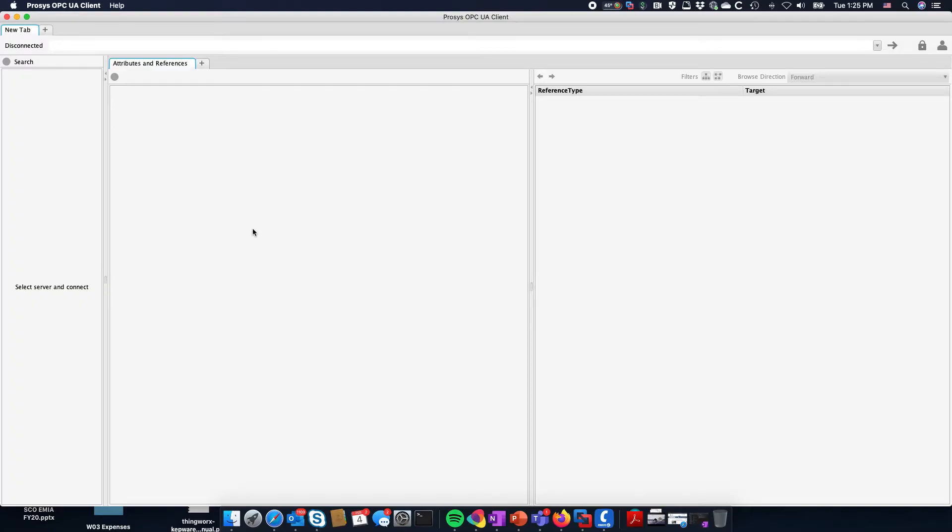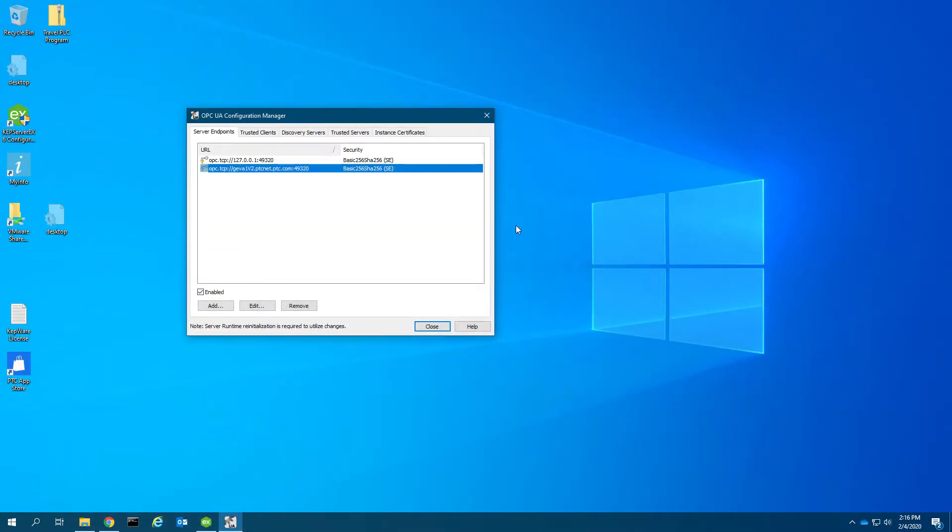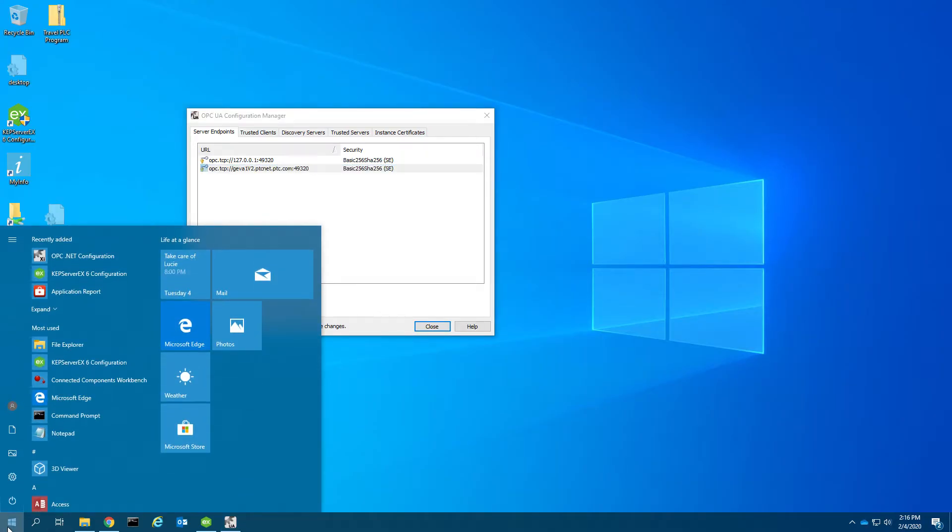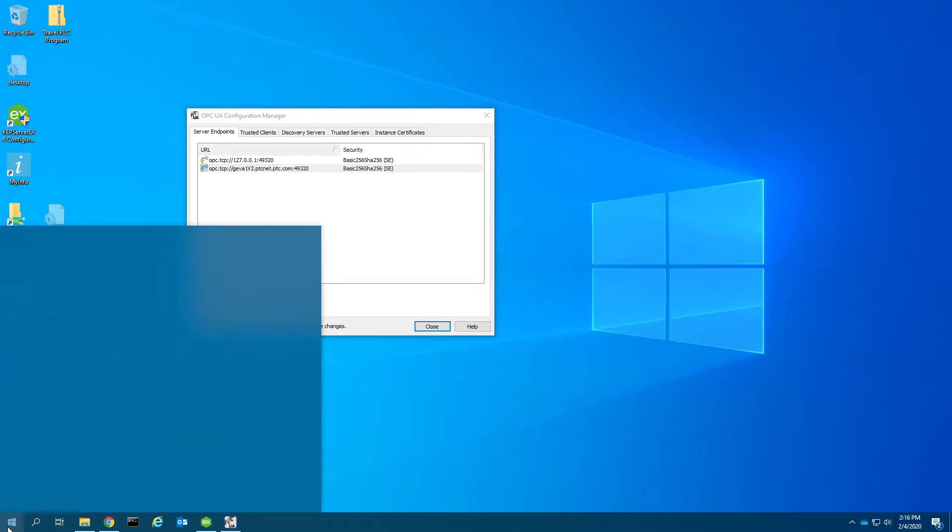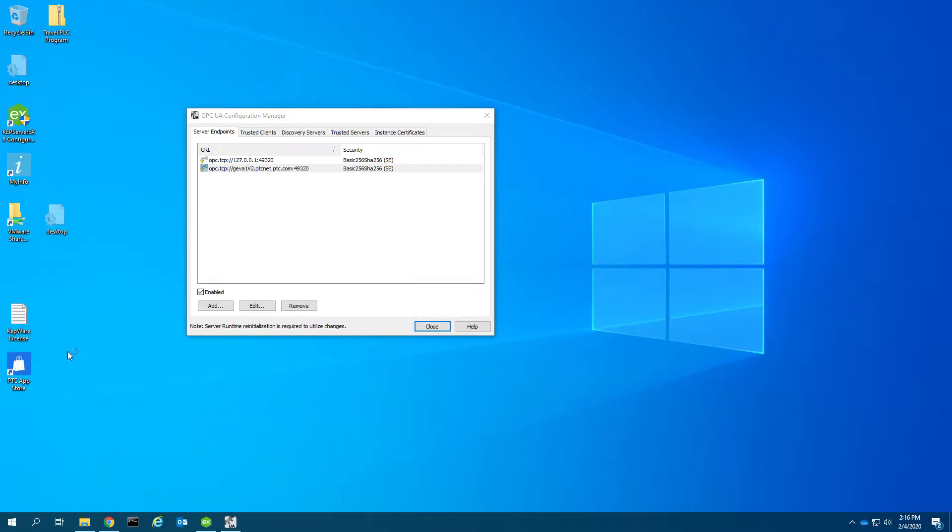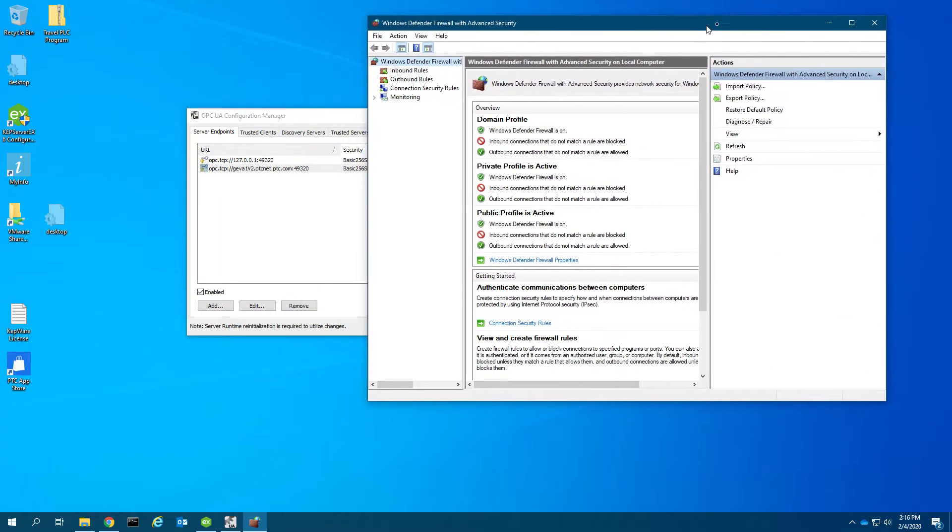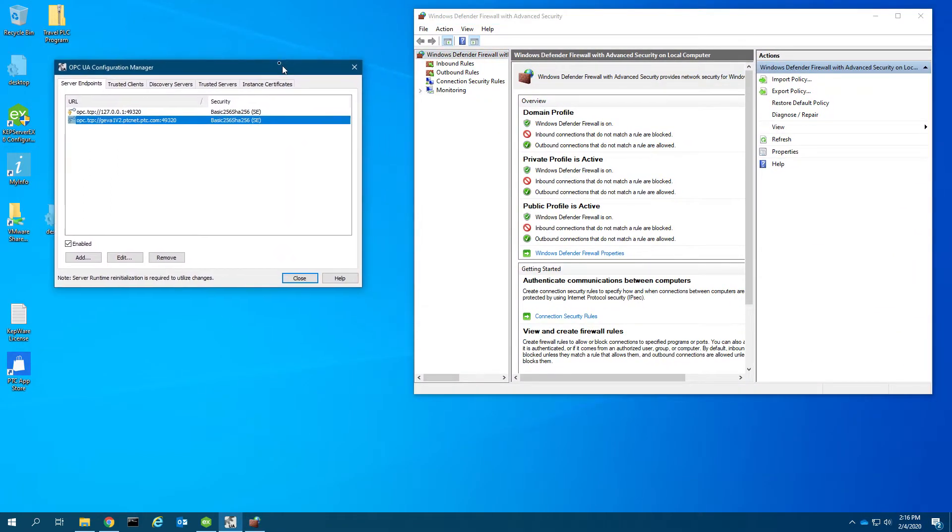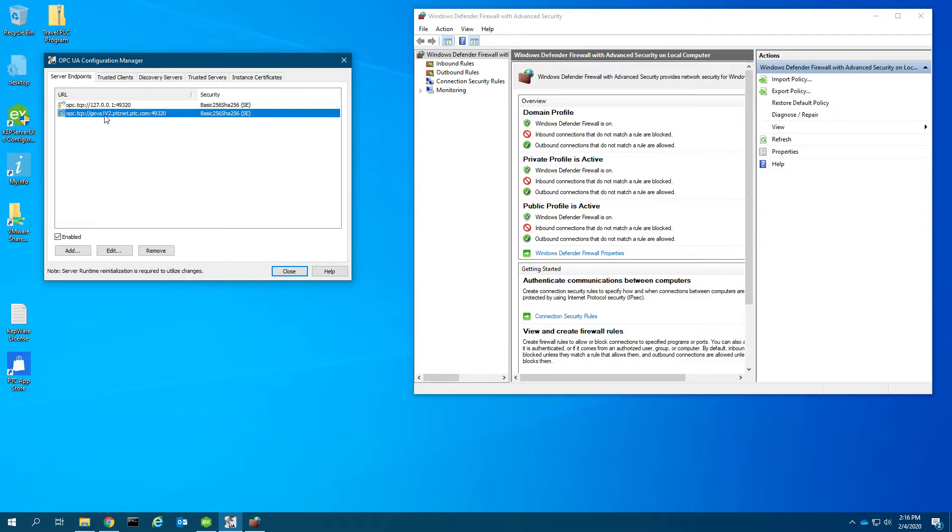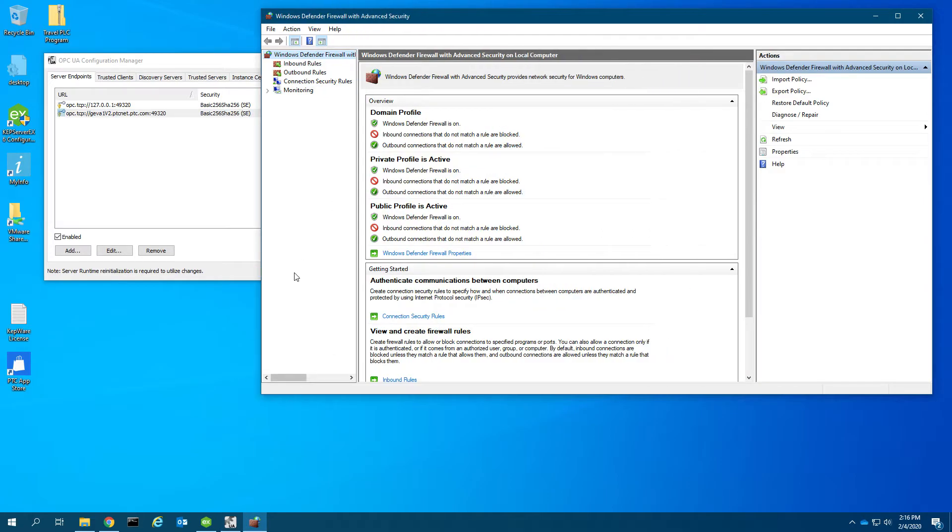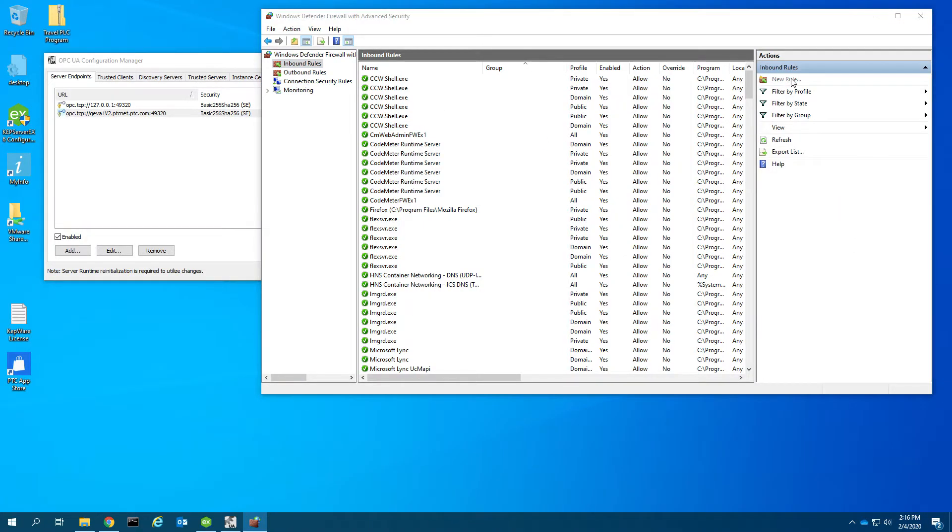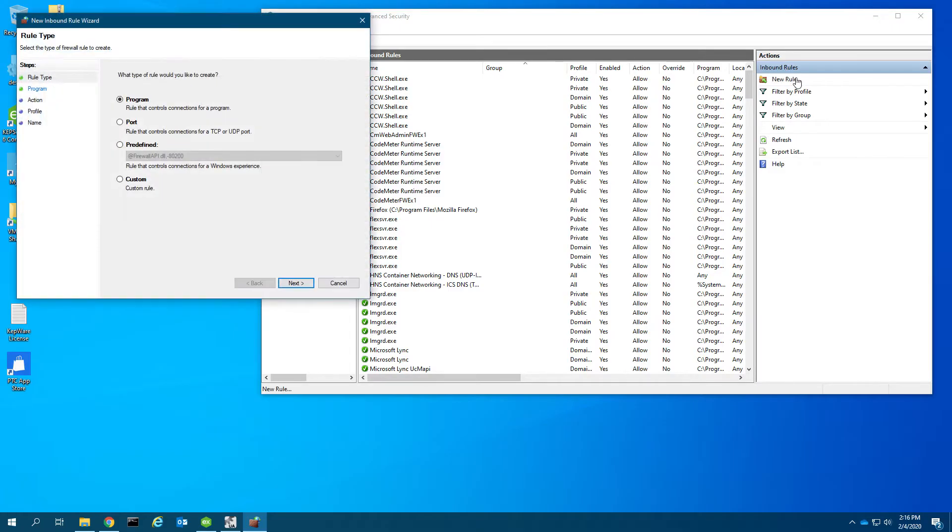Now we're going to hop over to our OPC client. We need to know the port, 49320. Actually, there's one more thing we need to do first: firewall. Windows Defender Firewall with advanced security. We did say we wanted to turn on the server interface to bind to this IP address, however Windows firewall is not going to allow us to communicate, so we're going to create a new inbound rule.